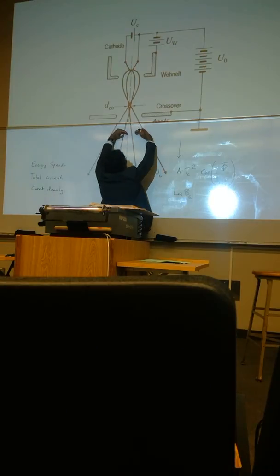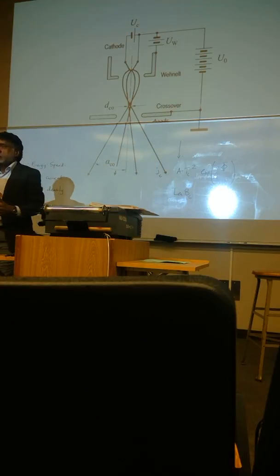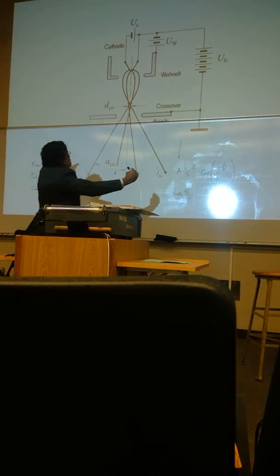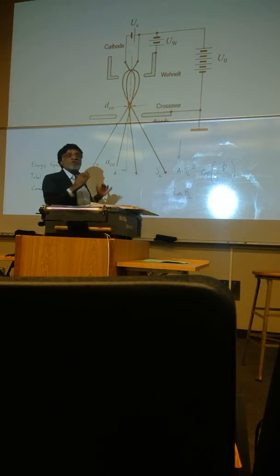It's just a current source. Can we control that alpha by moving the crossovers? You can. There are a number of ways of controlling alpha. It's true, by the crossover, or by making the hole smaller, the aperture size, or you can put subsequent apertures here that will control the alpha. That's called a condenser aperture. So you can put in these apertures afterwards to control the alpha.